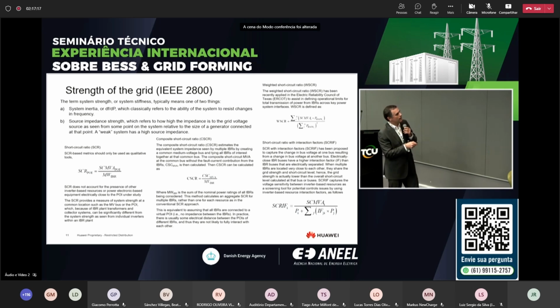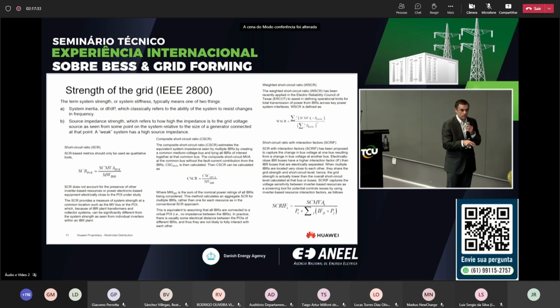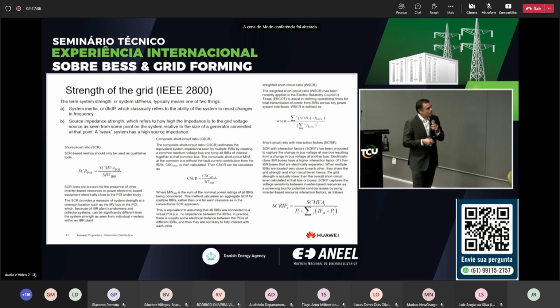There are some metrics, and the most typical one is the SCR, the short circuit ratio. The SCR is the short circuit power at the point of connection divided by the power of the plant you're connecting. When the grid is very strong and there aren't so many inverter-based resources, this is a good indicator. But when renewable integration is very large, it's not a good indicator, because you're not considering the effect of others. So we need something else.